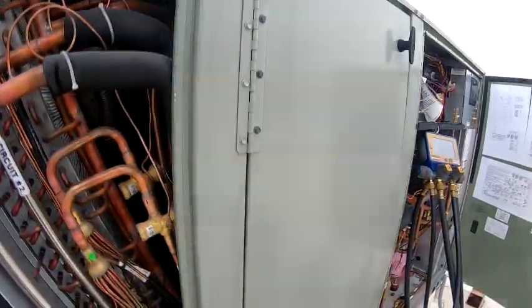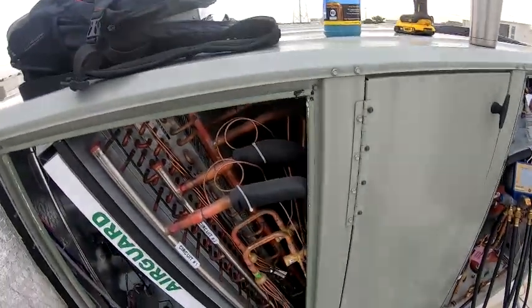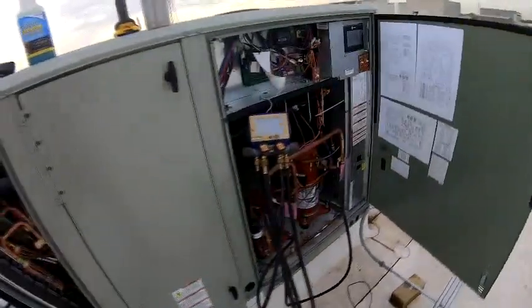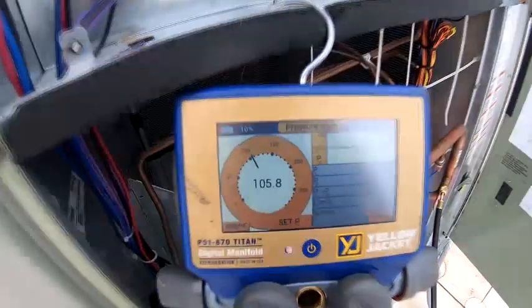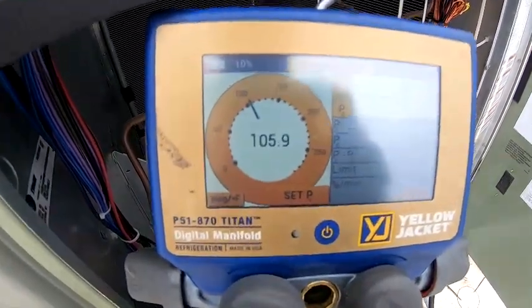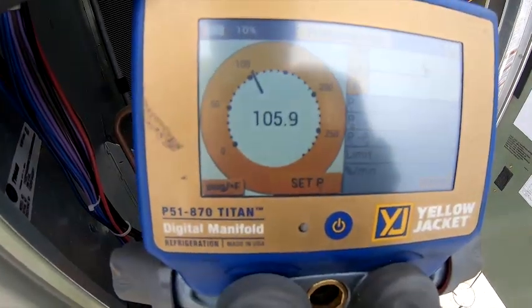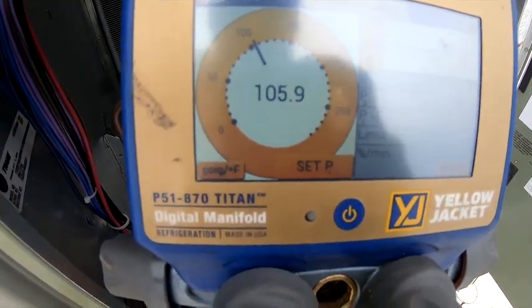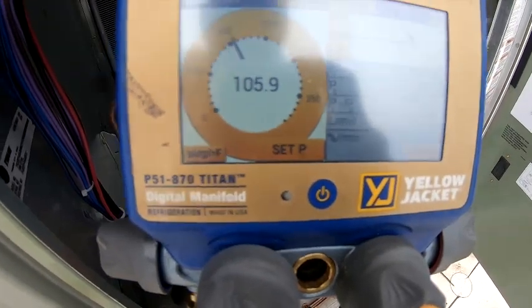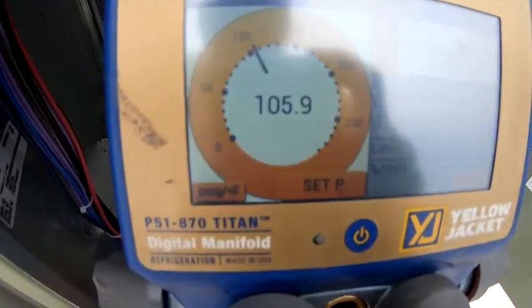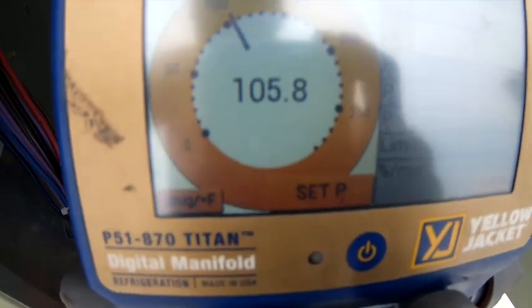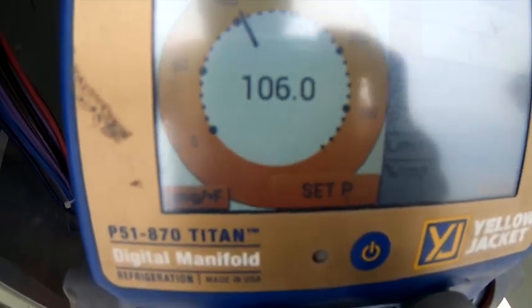But I'm gonna pull some panels off and start spraying these soap bubbles, try to check my joints, and gotta do some paperwork real quick. I'm gonna get back with you. But I think we got a small leak somewhere though. Let's see if it goes out. Cause I put 0.6 and it's kind of fluctuating. I think I said the allowable rate 105.3. Looking at about 105.89. Still trying to hang in at 106.